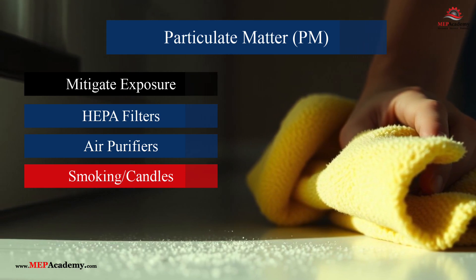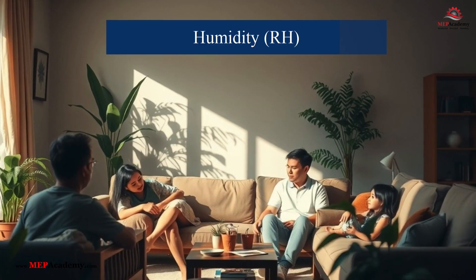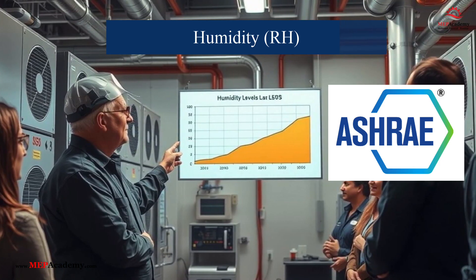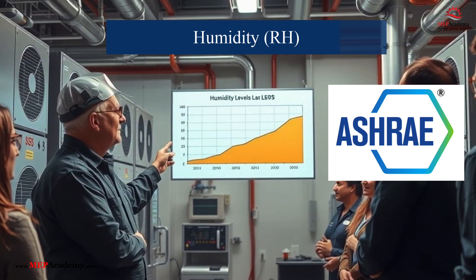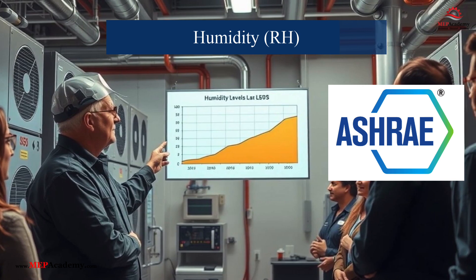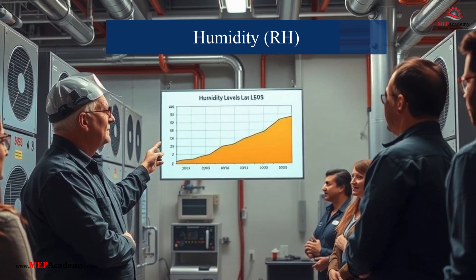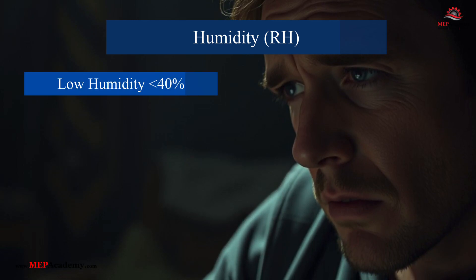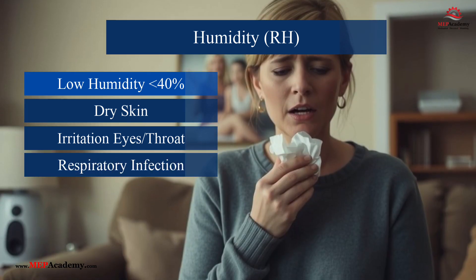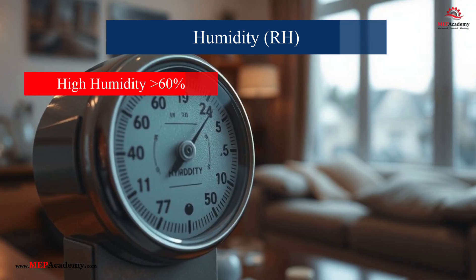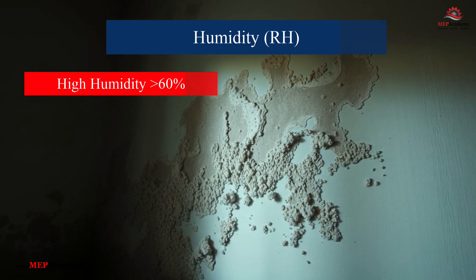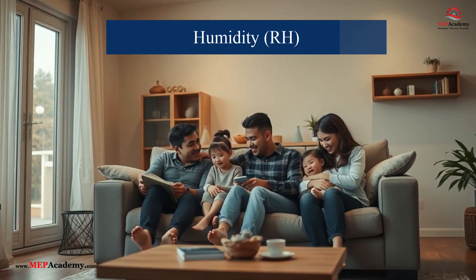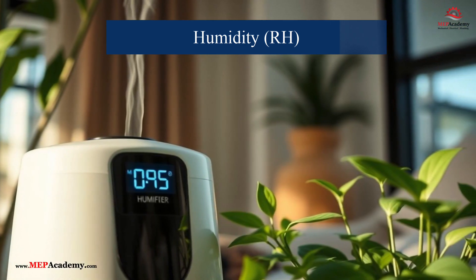Clean surfaces regularly to minimize dust accumulation. Humidity plays a significant role in maintaining a comfortable and healthy indoor environment. ASHRAE (American Society of Heating, Refrigerating, and Air Conditioning Engineers) recommends maintaining indoor relative humidity between 40% and 60%. Low humidity (less than 40%) can cause dry skin, irritation of the eyes and throat, and increased susceptibility to respiratory infections. High humidity (greater than 60%) promotes the growth of mold, mildew, and dust mites, which can trigger allergies and asthma.